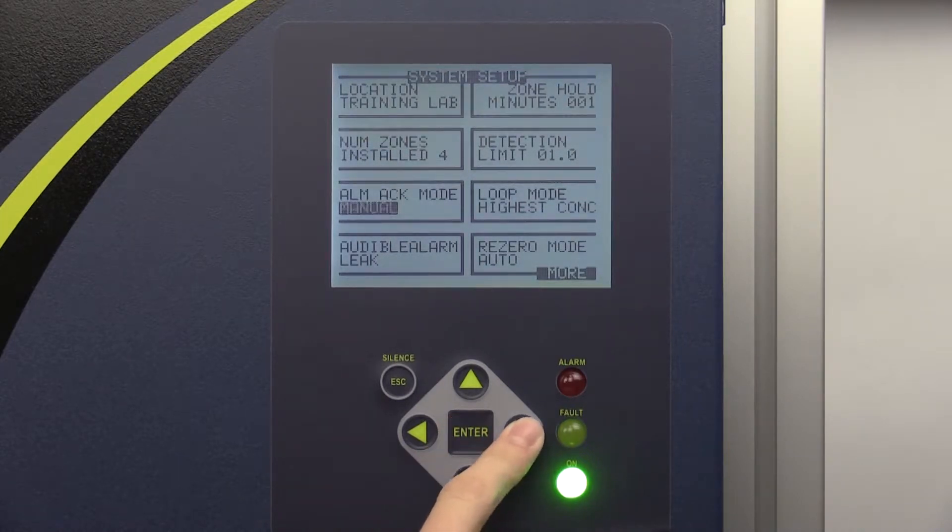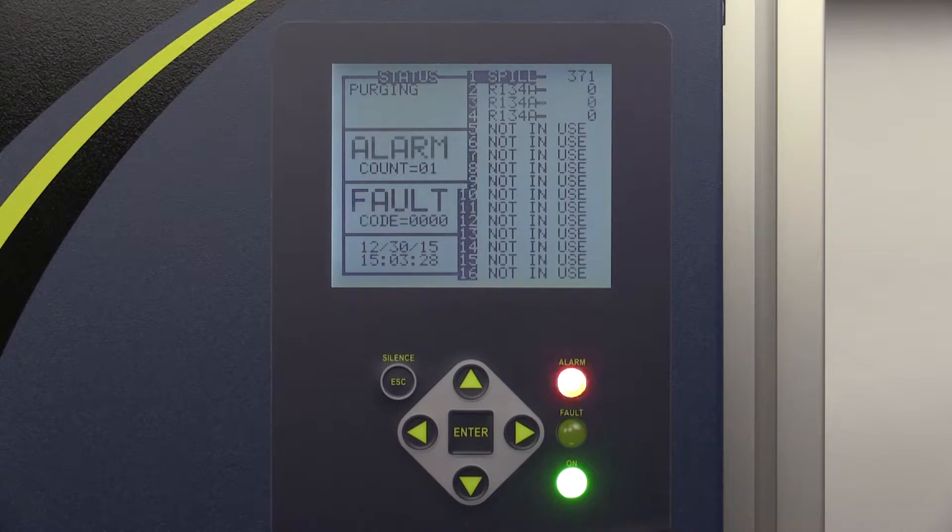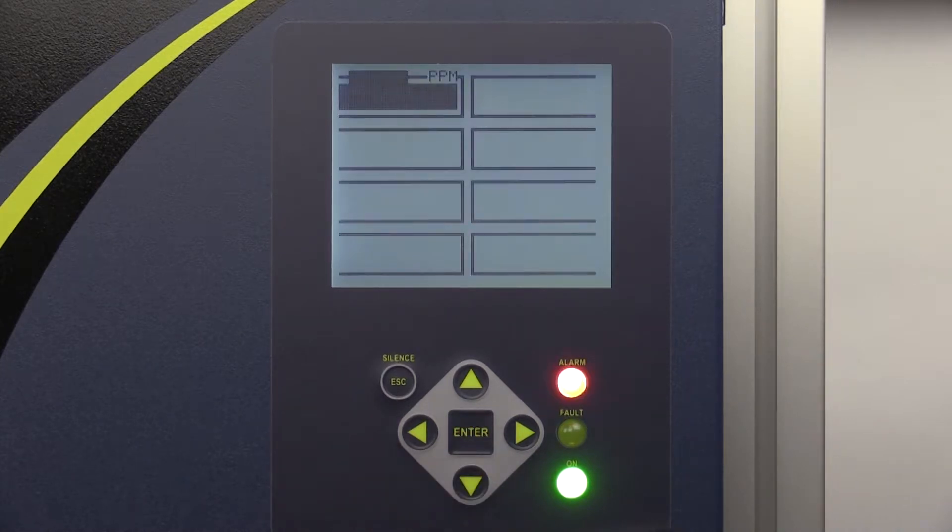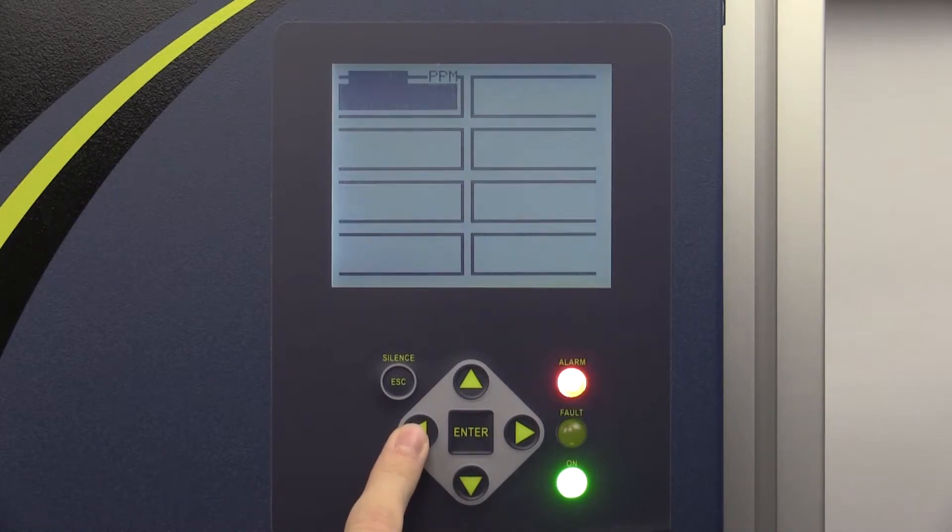When manual is selected, alarms must be manually acknowledged before they will turn off when the PPM reading reaches a safe level. To manually acknowledge an alarm, enter the alarm screen on the main data display. Press enter on the flashing alarm slot and then press the left arrow key to acknowledge the alarm. The next safe level PPM reading will disable the alarm.